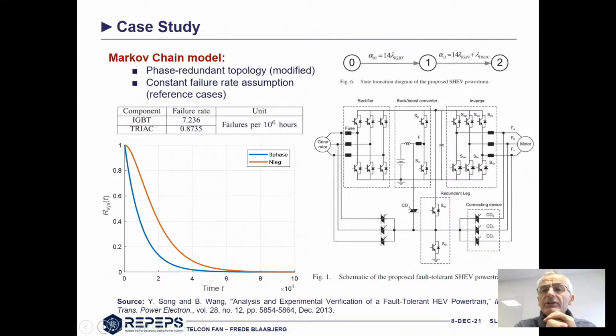Taking a more complicated example with fault tolerance built in: here we have a back-to-back converter, with a chopper, charger, or buck-boost converter, and a redundant leg providing fault tolerance on both sides. In total there are 14 IGBTs, and if one fails, the system is still up. If the triac fails, however, the system moves into a non-working state.